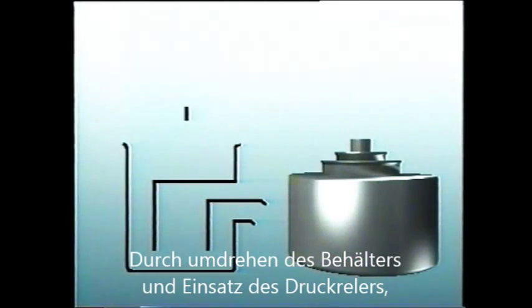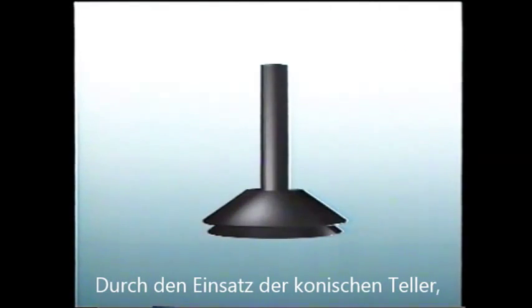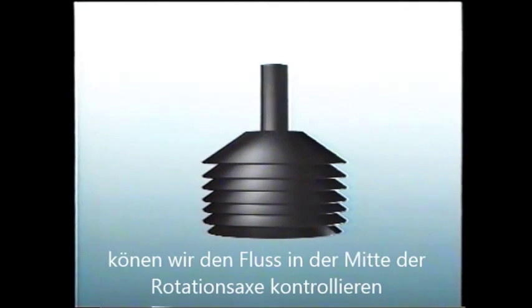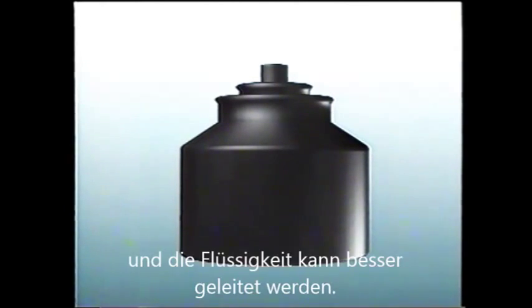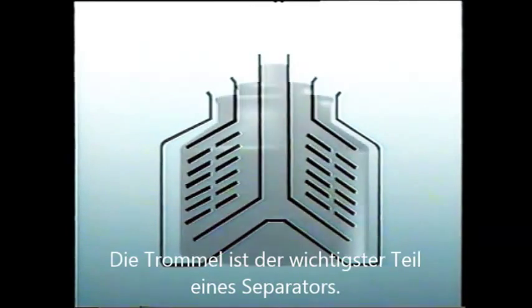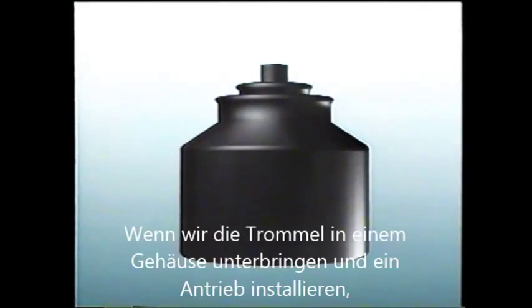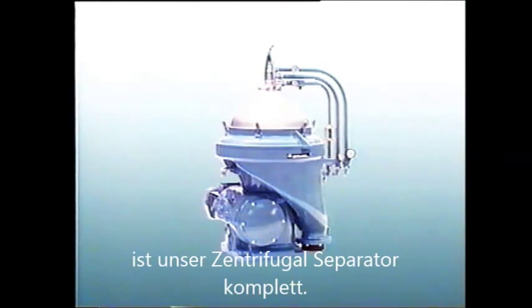The final improvement is to put holes in the disks in the region of the interface to speed up the liquid flow. By turning the dam from the balanced column tank into a ring or gravity disk, we can control the position of the neutral zone in the bowl. By turning the trays into conical disks or a disk stack, we have compensated for the smallest centrifugal force nearer the center of rotation and allowed the liquids to flow more freely. Finally, by making holes in the disks, we've improved the efficiency even more.